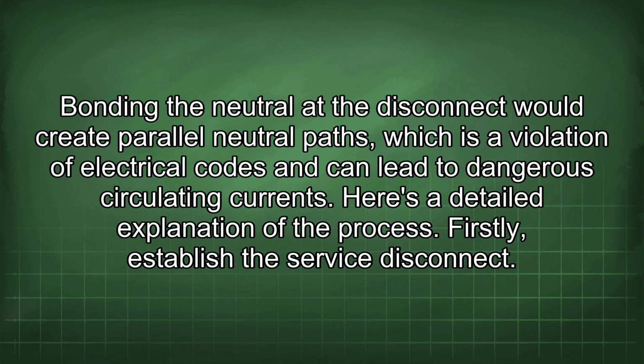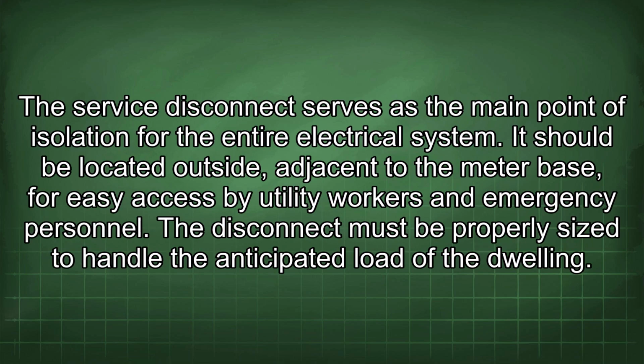Firstly, establish the service disconnect. The service disconnect serves as the main point of isolation for the entire electrical system. It should be located outside, adjacent to the meter base for easy access by utility workers and emergency personnel. The disconnect must be properly sized to handle the anticipated load of the dwelling.